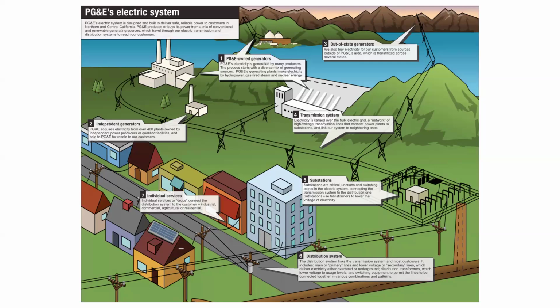What they do with that information is we then do analysis and studies to determine what is a symbolic representation of an average day in our territory. We take a reasonably high temperature or reasonable wind speed, and we do a calculation to say here is what our line ratings are—here's how much capacity we can pump through our lines before they overheat, degrade, anneal, or suffer any sort of degradation to the assets.